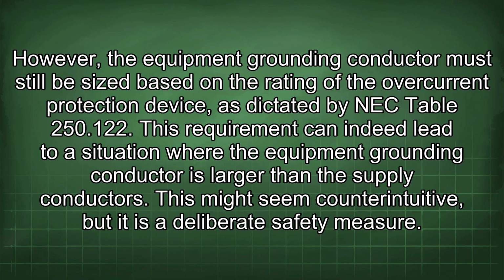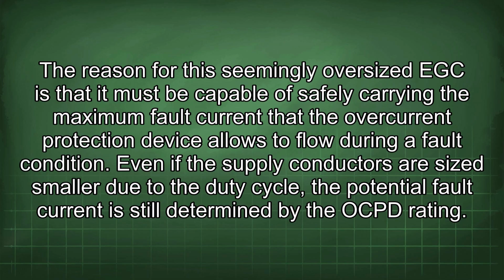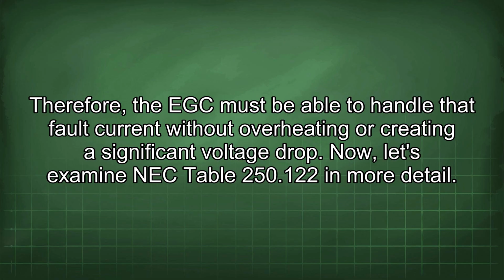This might seem counterintuitive, but it is a deliberate safety measure. The reason for this seemingly oversized EGC is that it must be capable of safely carrying the maximum fault current that the overcurrent protection device allows to flow during a fault condition. Even if the supply conductors are sized smaller due to the duty cycle, the potential fault current is still determined by the OCPD rating. Therefore, the EGC must be able to handle that fault current without overheating or creating a significant voltage drop.